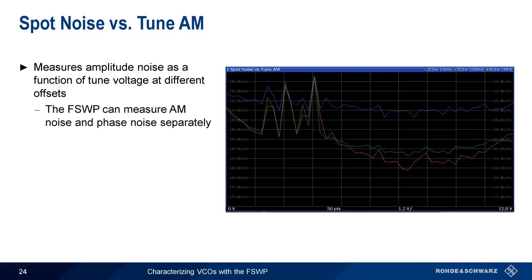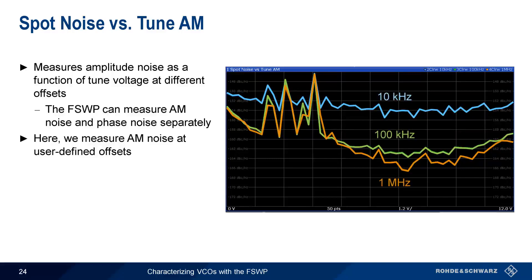These same parameters will need to be configured when making a spot noise versus tune AM measurement, which measures AM — or amplitude noise — as a function of tune voltage at different offsets. The architecture of the FSWP allows it to measure amplitude noise separately from phase noise. In this measurement, we're measuring and plotting amplitude noise at different user-defined offsets from the carrier — here at 10 kHz, 100 kHz, and 1 MHz. Note that AM noise is typically much smaller than phase noise.